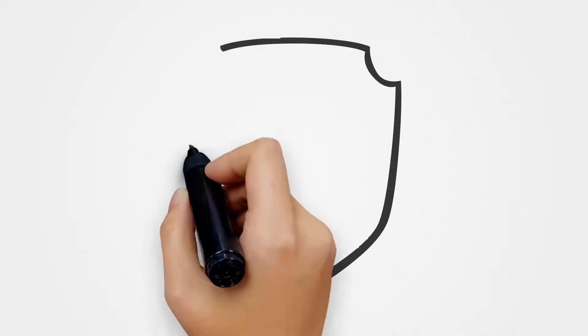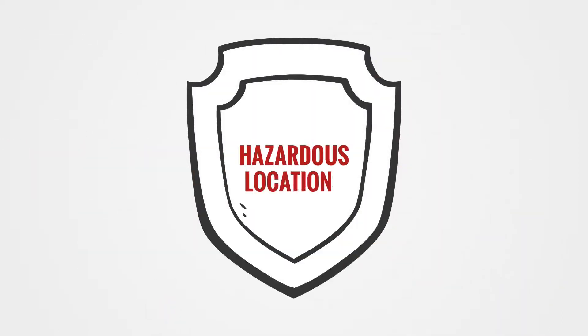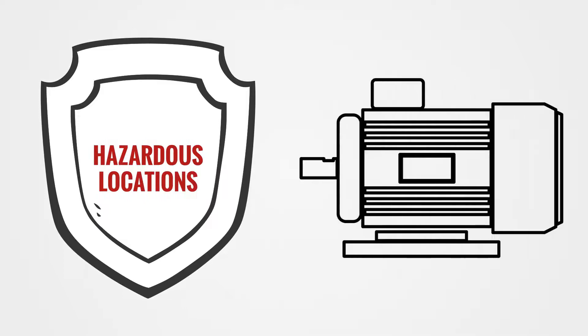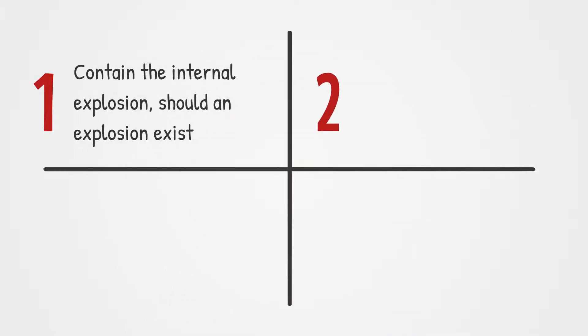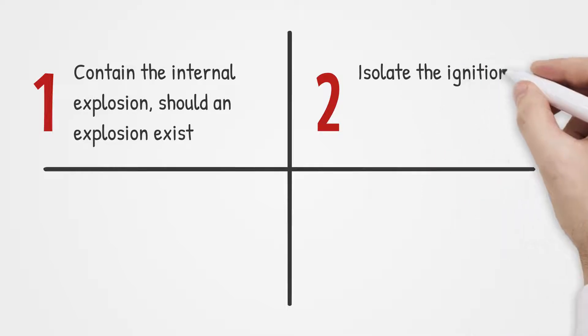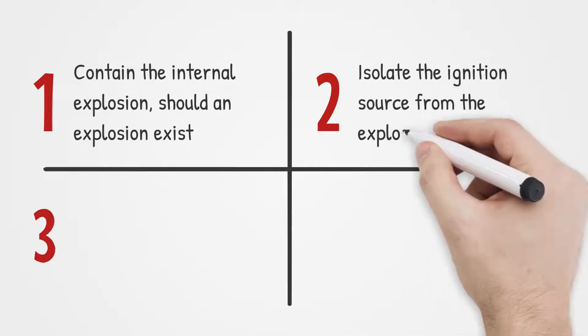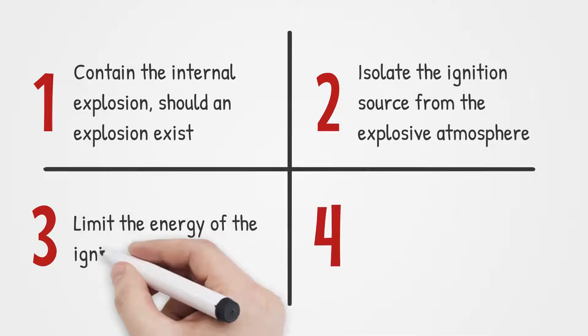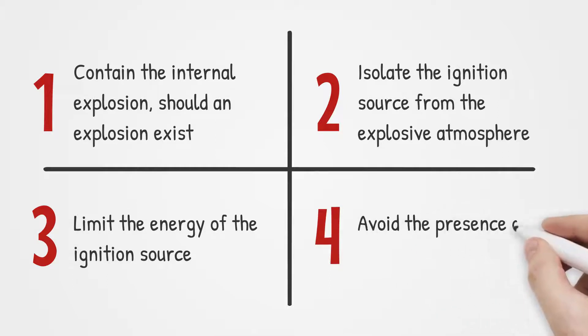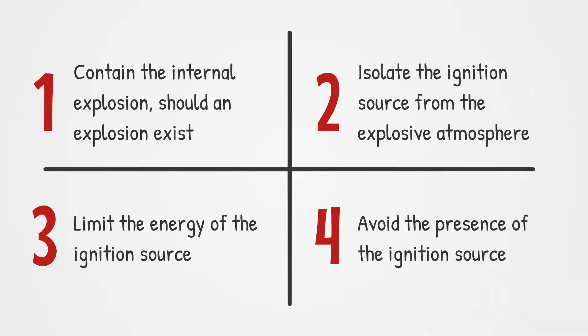Electrical equipment installed in hazardous locations must therefore be protected so explosions are prevented. Four methods are commonly used, sometimes in combination: contain the internal explosion should an explosion exist; isolate the ignition source from the explosive atmosphere; limit the energy of the ignition source; and avoid the presence of the ignition source.